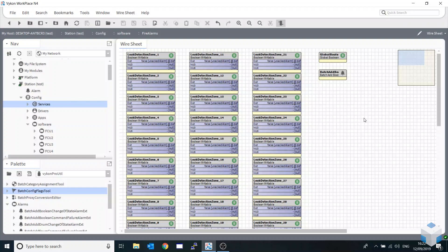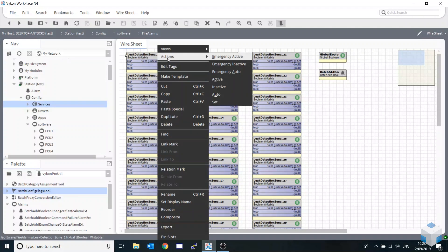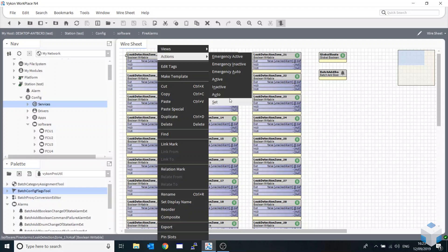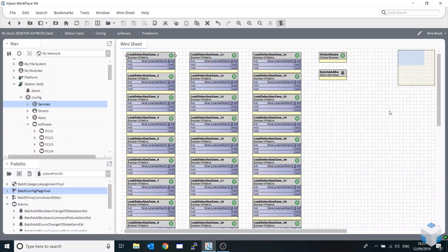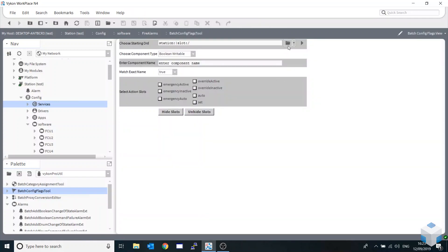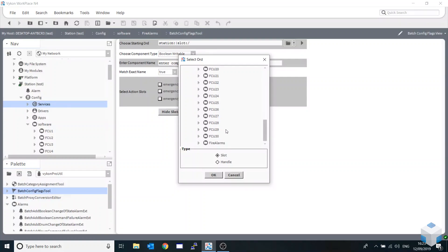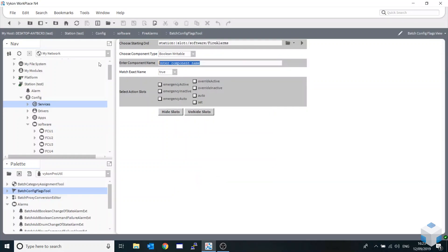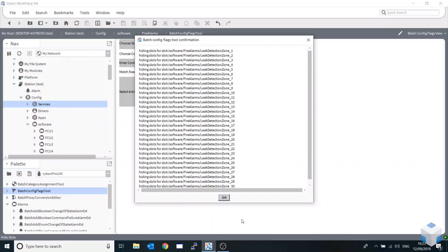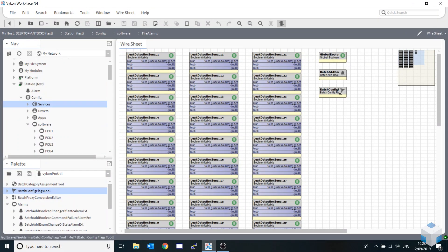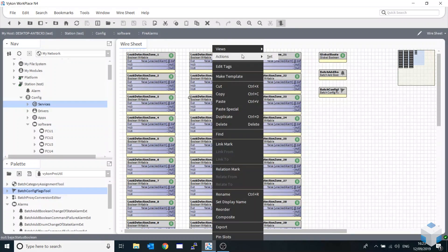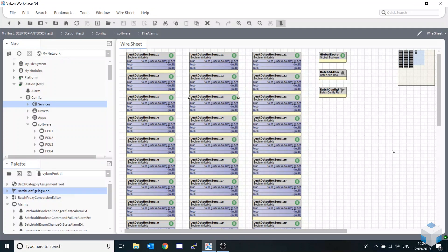Welcome back to the third part of our video. We'll be looking at our batch config flag tool. This gives us ability to hide commands on mass. Normally if you hang over a block and hit actions, we've got all these features. Some clients don't want everything there, some want everything removed. I'm going to show you how quick and easy it is using this block called the batch config flag tool. Drop that beneath our other modules. Again we'll be using a naming convention - go to the folder with our blocks, enter component name, hit a wild card. Now I'm just going to remove the emergency active and the override inactive/active. I'm going to remove all these blocks and auto, so on mass I'll be able to go to every single one of these blocks, remove these, and just leave set. I'm just going to click hide slot, come back with a confirmation.